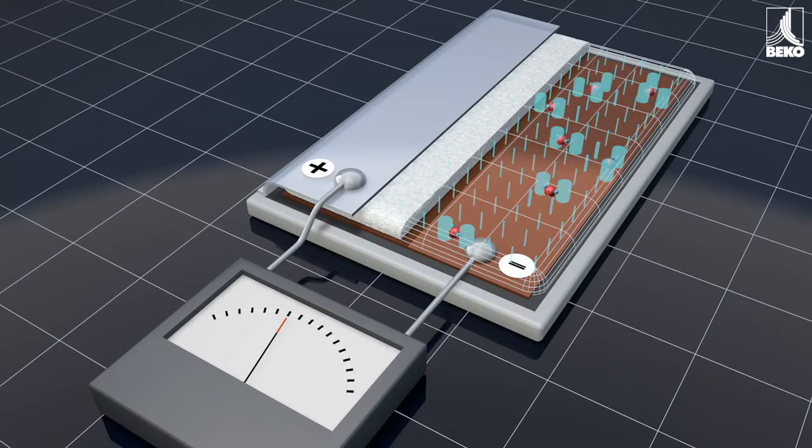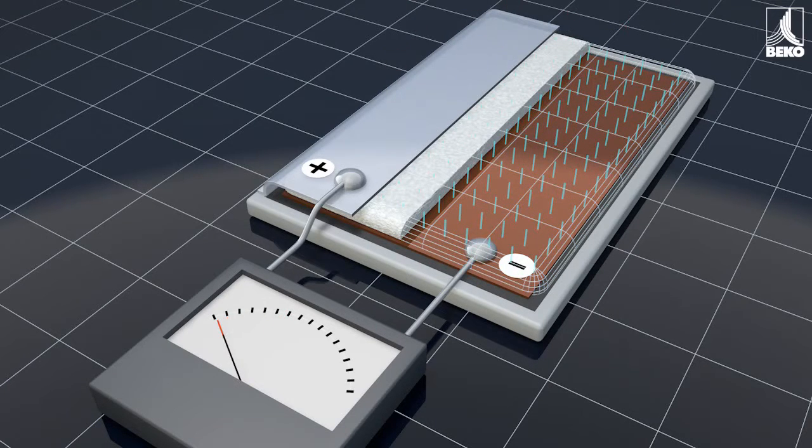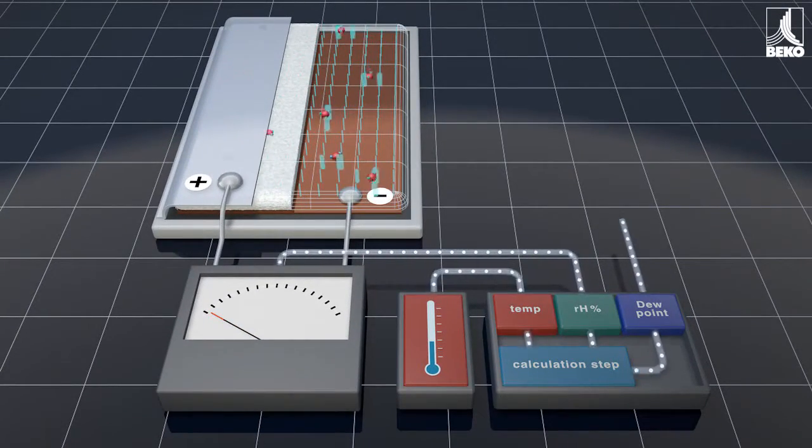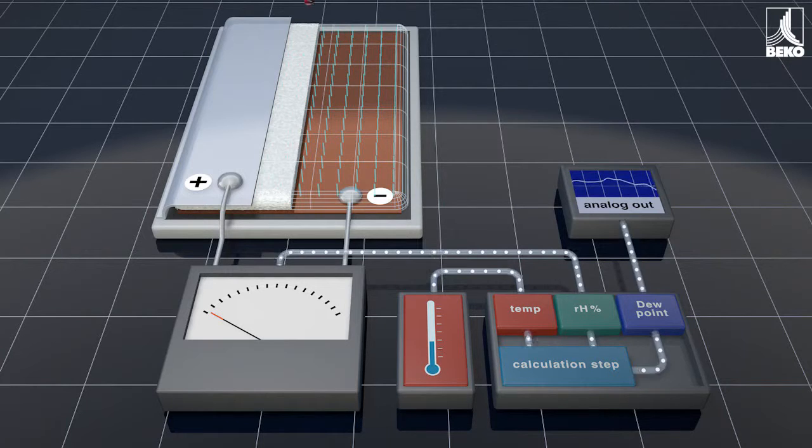The resulting capacitance is measured by means of an alternating voltage, and a moisture value is calculated. Depending on the process temperature, the actual dew point is derived from this moisture value.